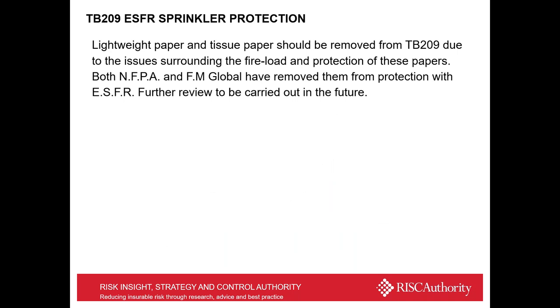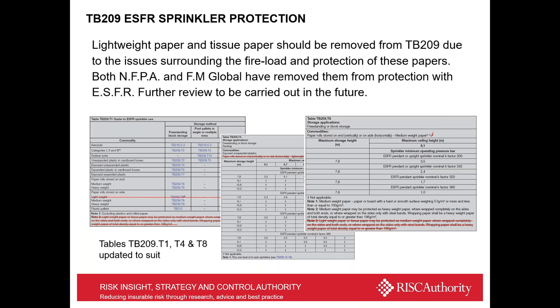There is also a removal of lightweight and tissue paper from TB209 based on the issues surrounding the fire load and protection of these papers. So both NFPA and FM Global have removed them from the protection. And what we have done is modified tables 1, 4 and 8 within TB209 to suit. So the new TB209 will have removed lightweight and tissue paper from the standard.